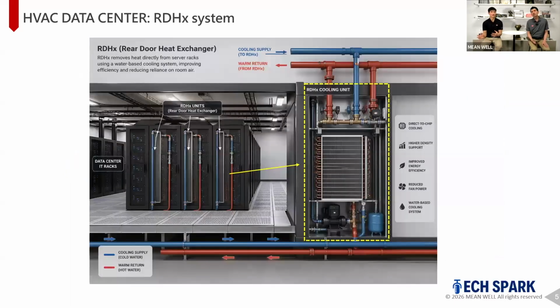So let's take a look at another peripheral, the rear door heat exchanger. Every data center basically needs this for basic liquid cooling to cool down the center. You see pipes going underneath the data center to do the cooling. The rear door heat exchanger is another element, basically a 30U size rack that's installed right next to or attached to the server rack. What it does is pull the heat out of the server rack, which has power supplies, servers, GPUs - a lot of heat.